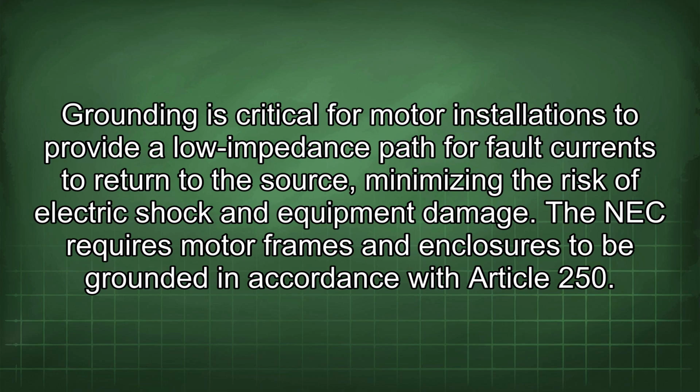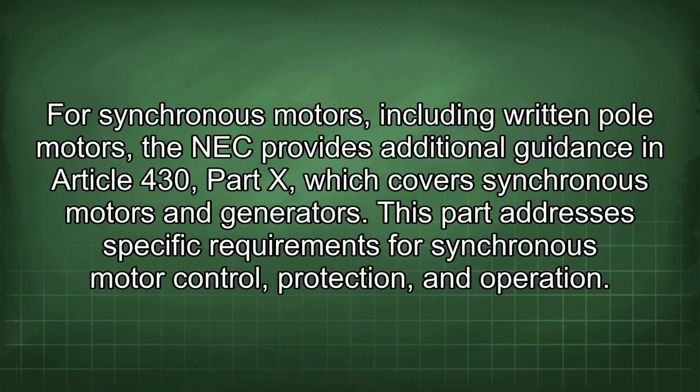Grounding is critical for motor installations to provide a low impedance path for fault currents to return to the source, minimizing the risk of electric shock and equipment damage. The NEC requires motor frames and enclosures to be grounded in accordance with Article 250. For synchronous motors, including written pole motors, the NEC provides additional guidance in Article 430 Part X, which covers synchronous motors and generators. This part addresses specific requirements for synchronous motor control, protection, and operation.